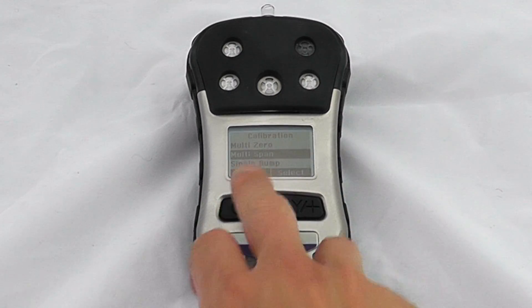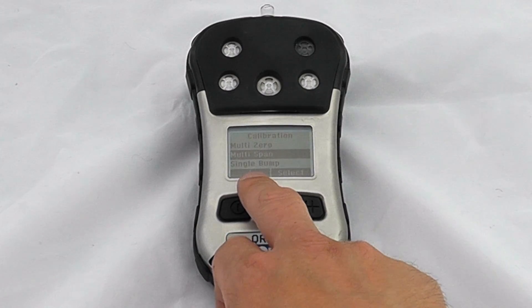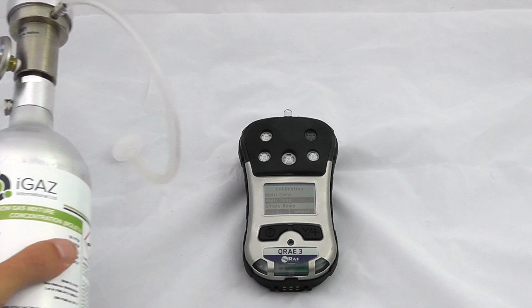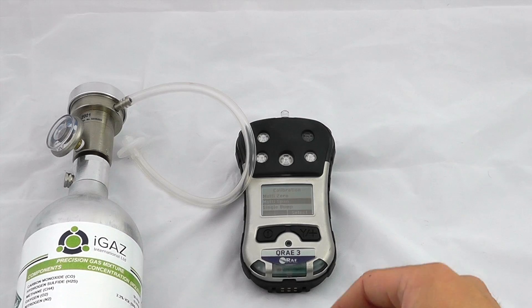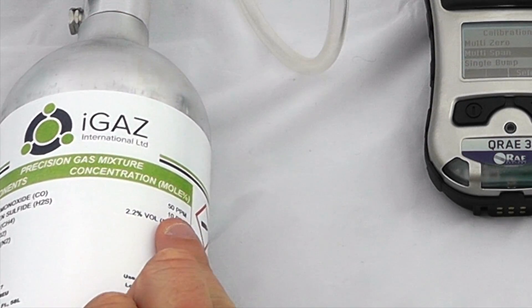Our calibration readings were successful on the zero calibration — everything has passed — so we can now exit that and do a multi-point span. You can also do single gas bumps or single gas spans. I'm using a standard four gas mix with an on-demand regulator, and this is one of the four gas mixes available from Safety Monitors. We happen to be using 50 parts per million CO.